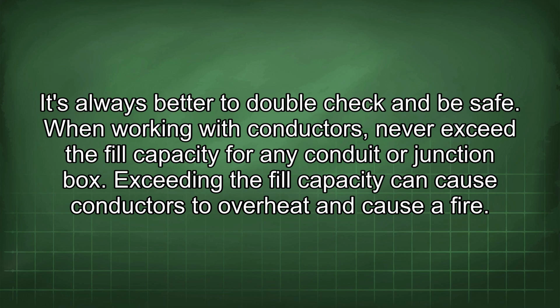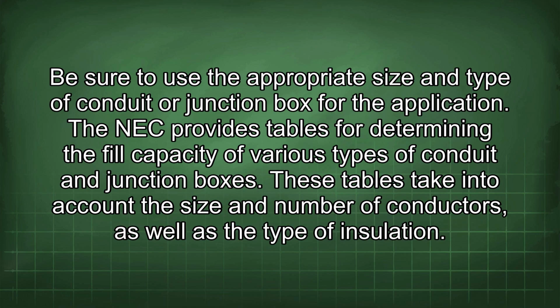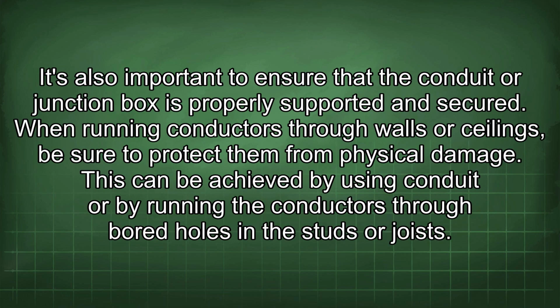When working with conductors, never exceed the fill capacity for any conduit or junction box. Exceeding the fill capacity can cause conductors to overheat and cause a fire. Be sure to use the appropriate size and type of conduit or junction box for the application. The NEC provides tables for determining the fill capacity of various types of conduit and junction boxes. These tables take into account the size and number of conductors, as well as the type of insulation. It's also important to ensure that the conduit or junction box is properly supported and secured.